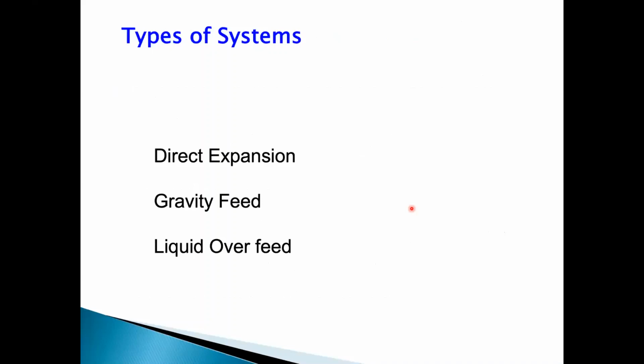Three types of systems are popular in ammonia refrigeration, particularly because we are talking about the vapor compression system. One is the direct expansion system, or DX system, which has been there since the inception of refrigeration. Then we have what is called a natural circulation or gravity feed system. And then we have a liquid overfeed system, popularly known in India as an ammonia pump overfeed system or ammonia pump feed system.